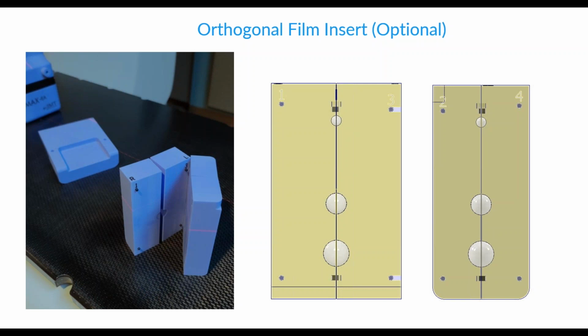We also have another optional insert, which is an orthogonal film insert, and it has 3 targets. So obviously it has 2 film planes and 3 targets. And again, this also fits into the cavity of the Max EA. So as you can see with the removable cover, once you've set up the Phantom, especially with the thermoplastic mask, you can easily just remove the cover, put the Winston Lutz insert in, do your daily Winston Lutz test with that setup, and then remove that insert, and then go ahead and do your film analysis.